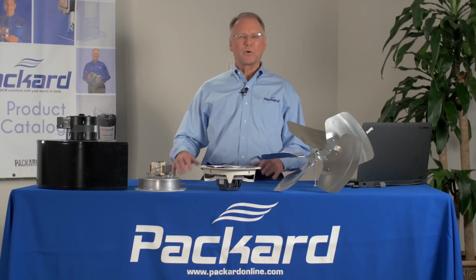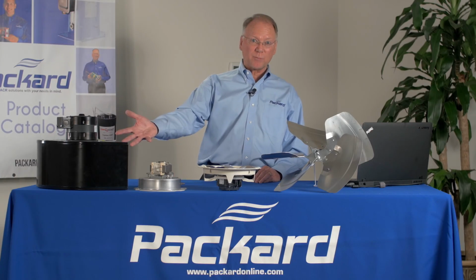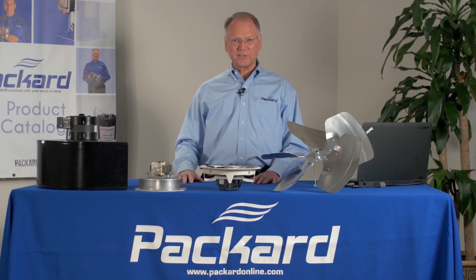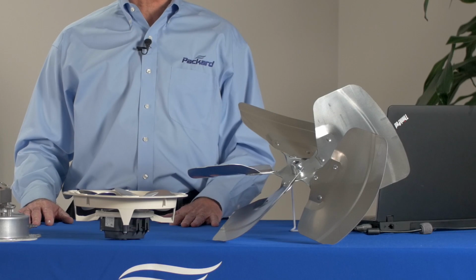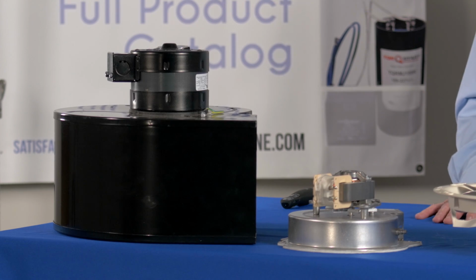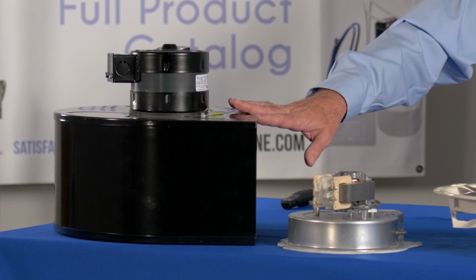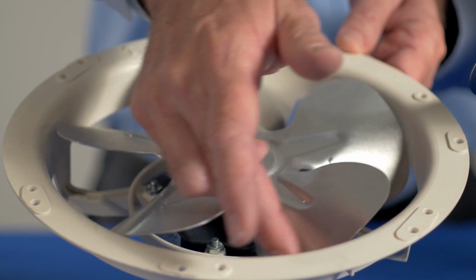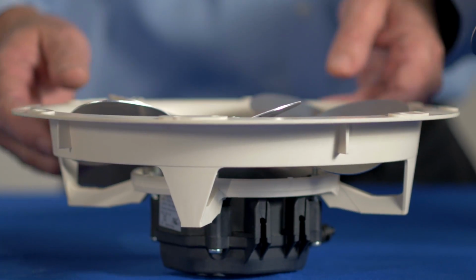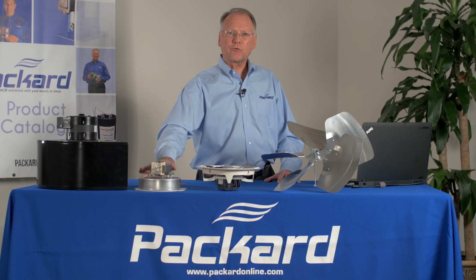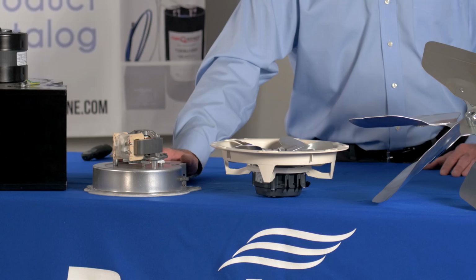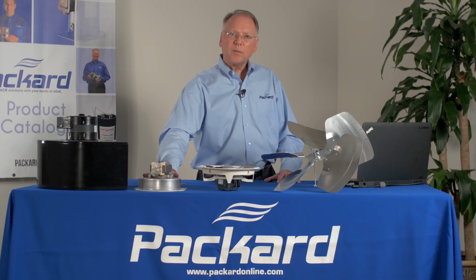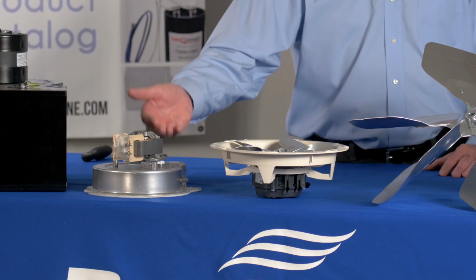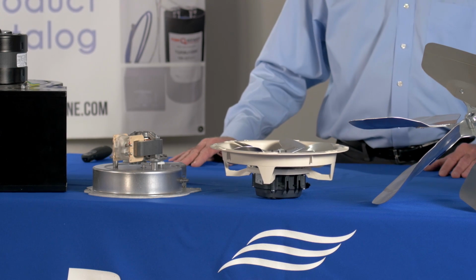In summary, airflow is a critical component of heating and air conditioning. Where there is higher static pressure, a blower may be used. Where the static pressure isn't as high, a fan blade is typically used. For proper performance of the blower, a housing is required, and for proper performance of a fan blade, an orifice is used. Draft inducers are critical components in furnaces. It not only provides a clean burn, but also removes the gases that may be hazardous to our health.